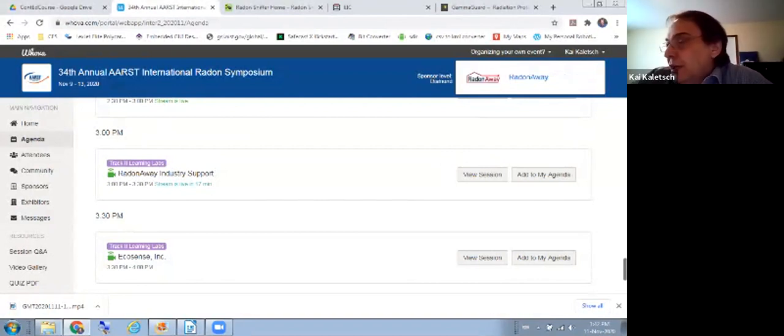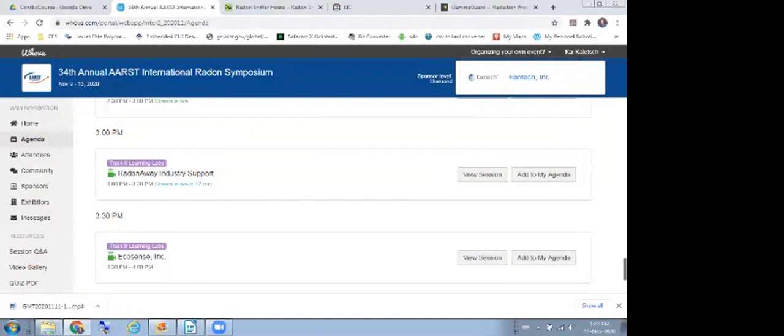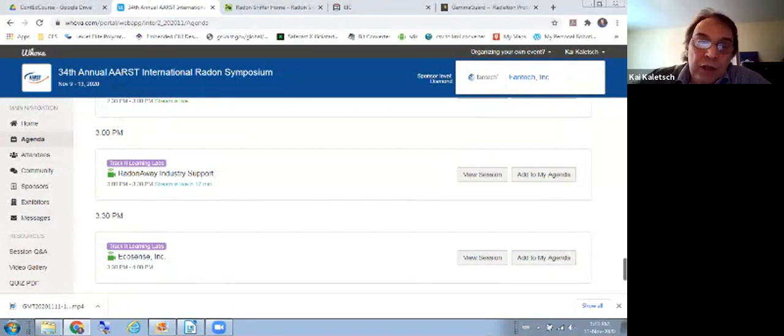You still will have the thoron. You won't get the thoron progeny. It is a confounding agent. We are working on a little module for that that'll actually try and quantify how much thoron you'll have. But really, the idea with the thoron is if you're working fast, if you're just going 90 seconds one hole, 90 seconds to the next hole, the algorithm doesn't have to work so hard. So all of the buildup and stuff like that isn't that important anymore.